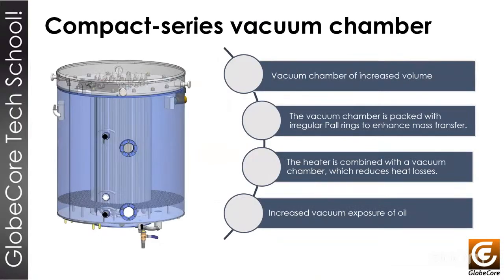You can see here we have the heater elements in the center of the tank, and this is two tanks, which means the oil will come inside the central tank and start to fill it, and will have contact with the different resistors. When these resistors start to heat, the oil will start to go up inside this tank by the vacuum effects. When this oil reaches the high level inside, we have a special cover that will move the oil from the central tank to the external tank.